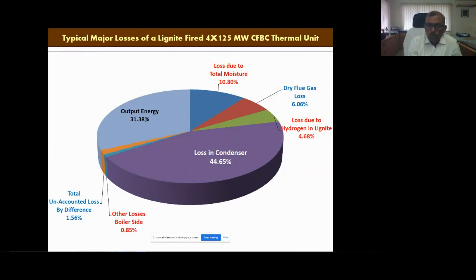Then the output is 31.38%. And there is loss due to total moisture. Moisture is a major one, because our fuel is lignite, where the moisture is around 43 to 52%. This causes a major impact on boiler efficiency. Dry flue gas loss is around 6.06%. Loss due to hydrogen in lignite is 4.68%. Other boiler-side losses are 0.85, which constitute the sensible heat of ash, moisture present in air, radiation loss and unburned carbon loss, and unaccounted loss is 1.56. So the heat rate varies almost 2600 to 2700 for this CFBC power plant that we are operating, 4 into 125 megawatt. The major factor is the moisture, which is causing major loss to the efficiency.